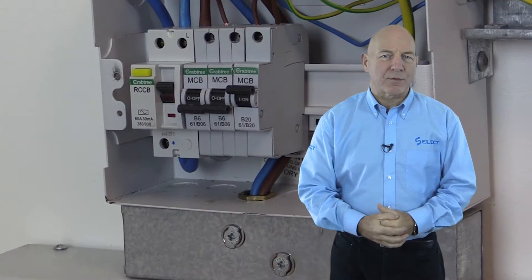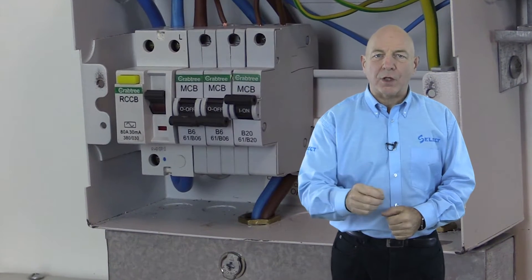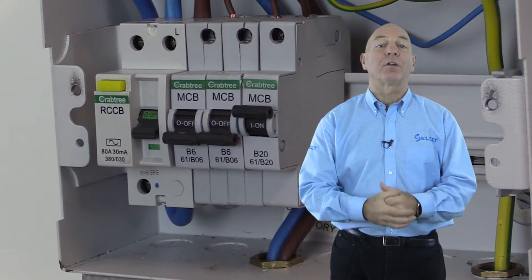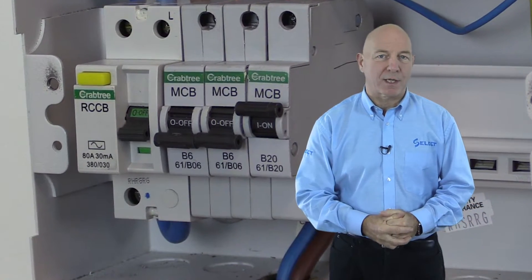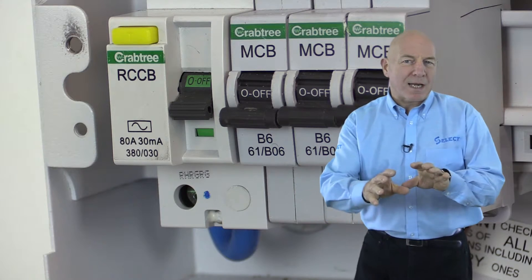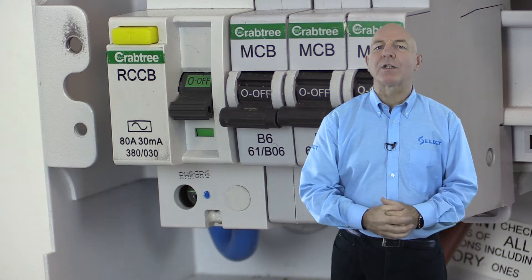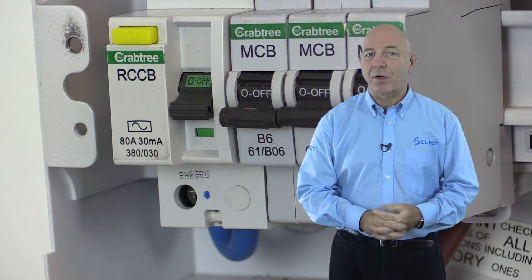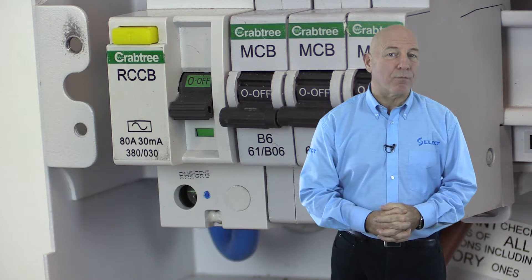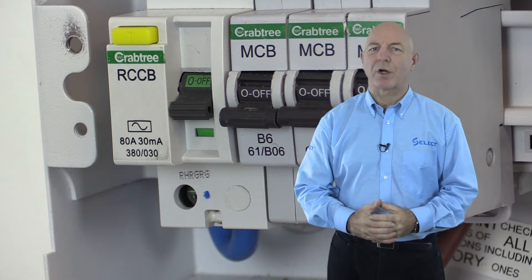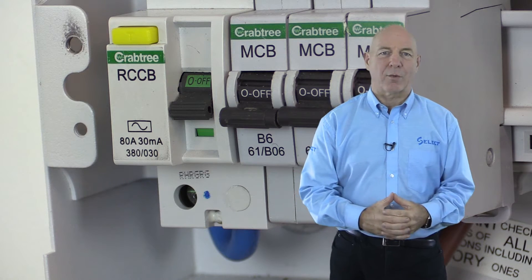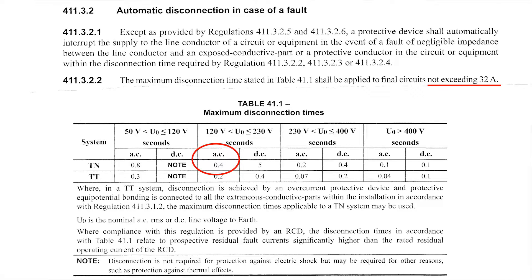Automatic disconnection of supply requires that under fault conditions the circuit breaker or fuse will operate and disconnect the supply to the line conductor within a specified maximum permitted disconnection time. For a TN earthing system, the maximum disconnection time for a final circuit with a protective device rating not exceeding 32 amps is 0.4 seconds, and for a distribution circuit and for a circuit with a protective device rating exceeding 32 amps is 5 seconds, as per section 411 of BS 7671.